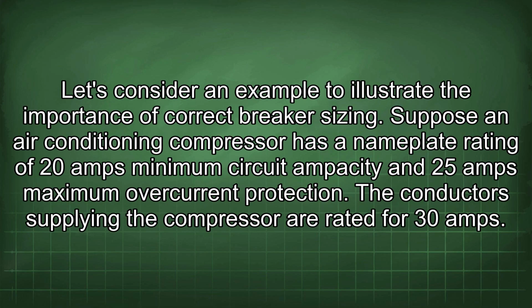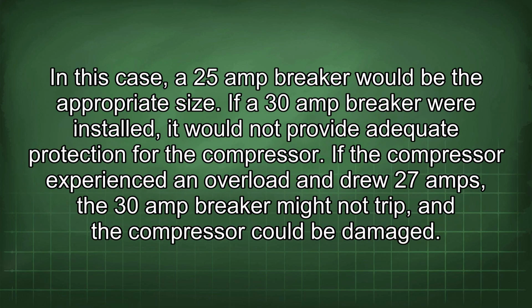Let's consider an example to illustrate the importance of correct breaker sizing. Suppose an air conditioning compressor has a nameplate rating of 20 amps minimum circuit ampacity and 25 amps maximum overcurrent protection. The conductors supplying the compressor are rated for 30 amps. In this case, a 25 amp breaker would be the appropriate size.